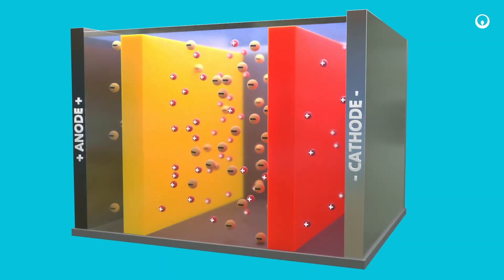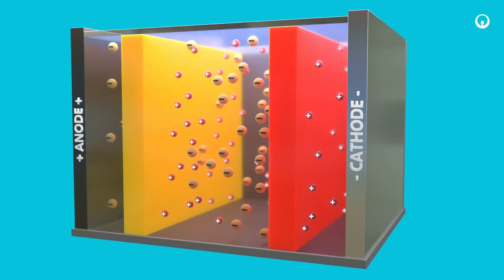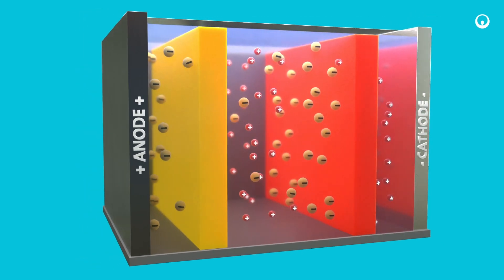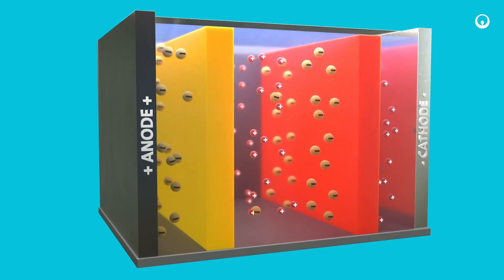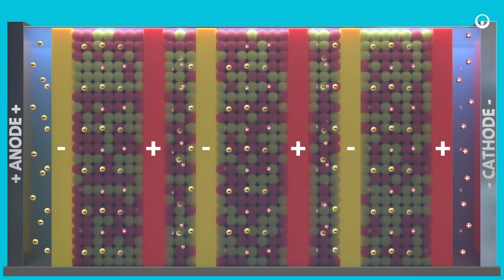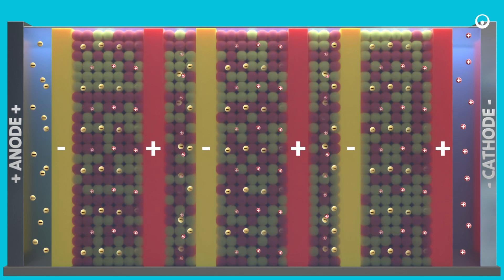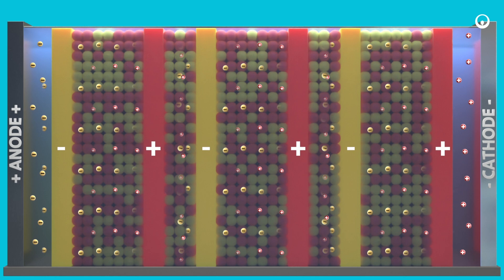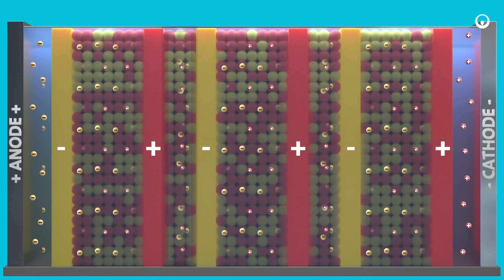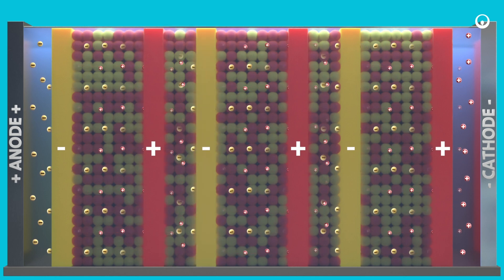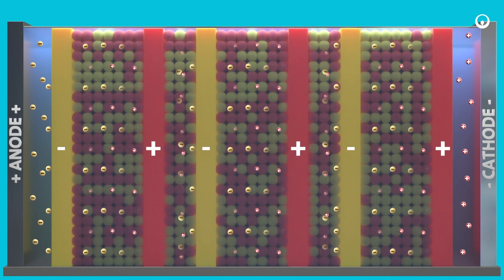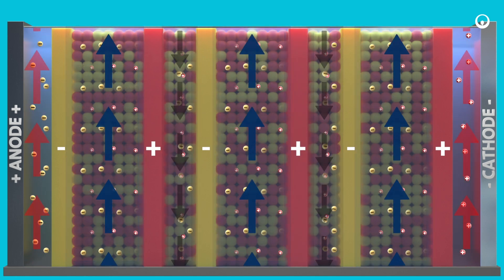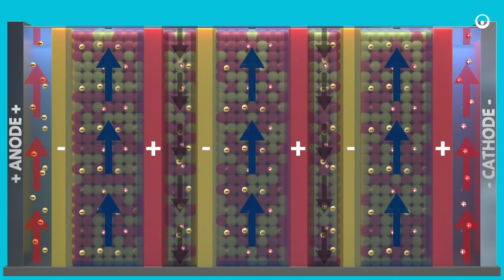Membranes are ion-selective as a bridge. Cation membrane will only allow cations through, while anion membrane only allows anions through, flowing to the opposite electrode. Each EDI cell pair contains one demineralizing compartment consisting of a dilute spacer and resin, one concentrating compartment consisting of concentrate spacer and resin, one anion membrane, and one cation membrane. An EDI stack is composed of multiple cell pairs, creating parallel duplicate demineralizing compartments.